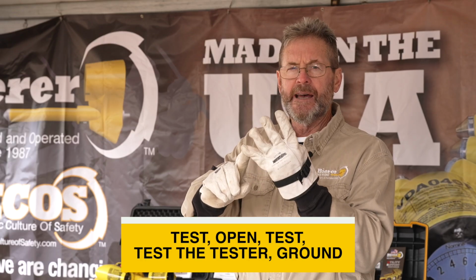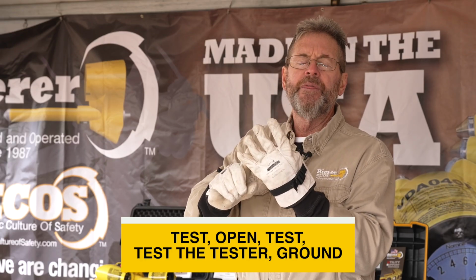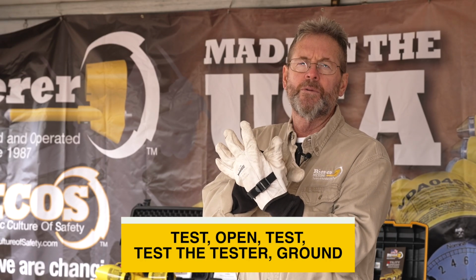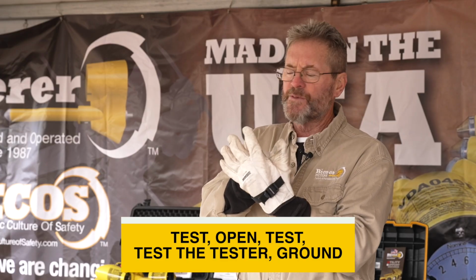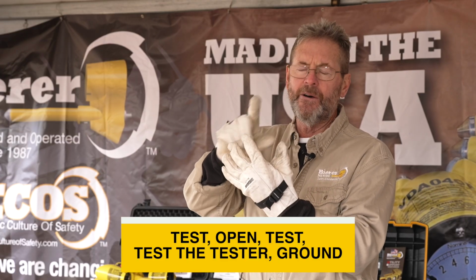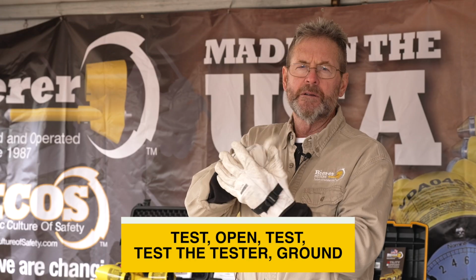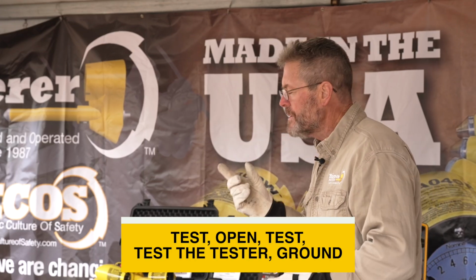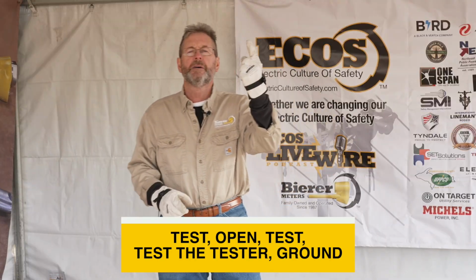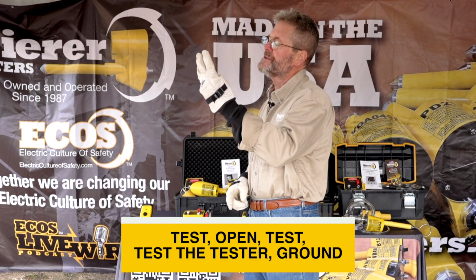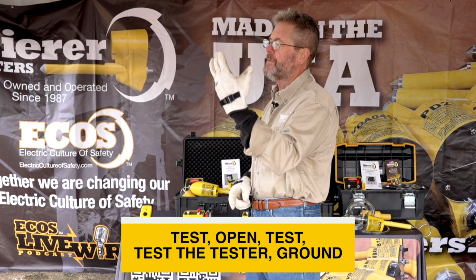Then we're going to test the tester. Then we're going to go ahead and ground. All right? Once we do that, we've got our lockout, tagout. We've got our clearance now. Perfect. So we always want to do those steps. We're going to test, open, test, test the tester, ground, every single time. All right, folks? It's awesome. It's much safer.